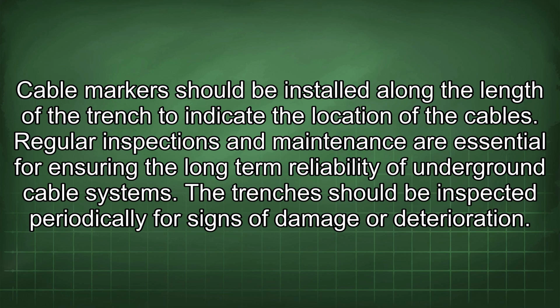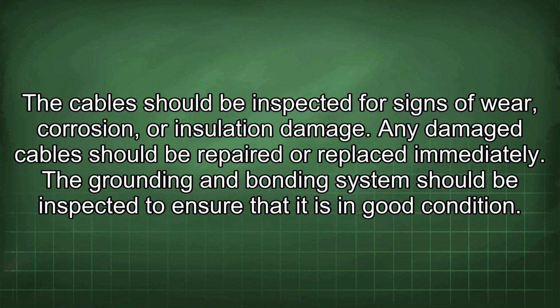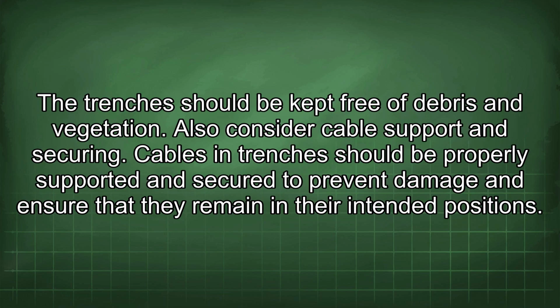Regular inspections and maintenance are essential for ensuring the long-term reliability of underground cable systems. The trenches should be inspected periodically for signs of damage or deterioration. The cables should be inspected for signs of wear, corrosion, or insulation damage. Any damaged cable should be repaired or replaced immediately. The grounding and bonding system should be inspected to ensure that it is in good condition. The trenches should be kept free of debris and vegetation.